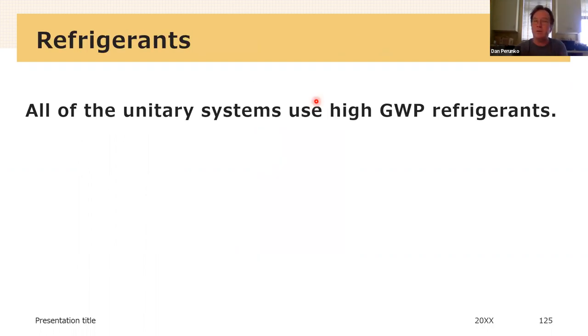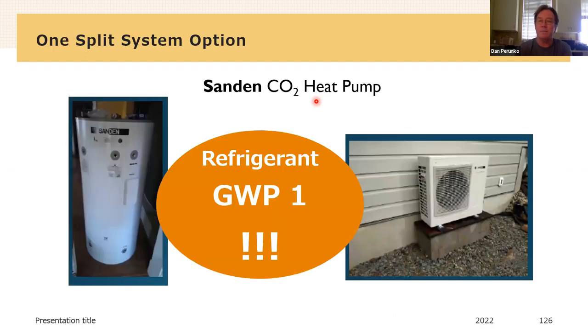All of those machines that I showed you use high global warming potential refrigerants. And generally speaking, there's no annual service. So nobody should be hooking up to them and releasing refrigerant. So that's good, even though the refrigerants are not great. This is better. This uses carbon dioxide as its refrigerant. And in order for carbon dioxide to work as a refrigerant, it has to function at really high pressures, like 3000 PSI. So the entire refrigerant cycle is in the outside unit and the hot water is in the tank inside.